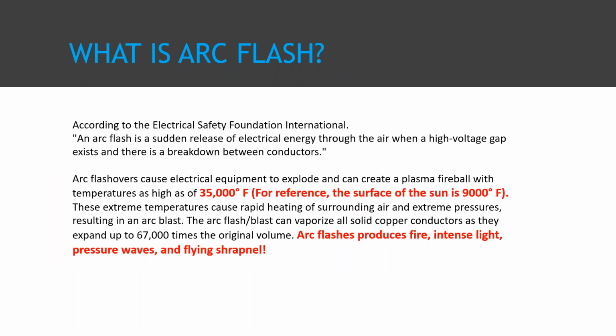So what's an arc flash? Really, it's a sudden release of electrical energy through the air. And the reason it causes injury, hospitalization, and death is it creates a plasma fireball with super high temperatures. We're talking like 35,000 degrees F. Surface of the sun is only 9,000. So we're talking unbelievably high temperatures. We're also talking an explosion. So that rapid heating causes a lot of extreme pressures, and that results in an arc flash or an arc blast. All right, that can vaporize any of the components of the switchgear. The copper conductors expand up to 67,000 times the original volume.